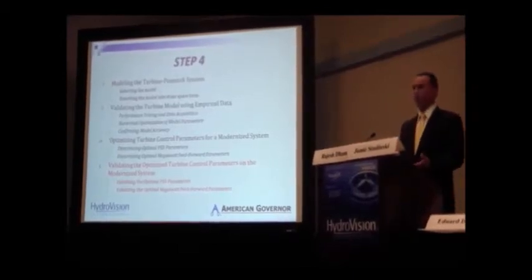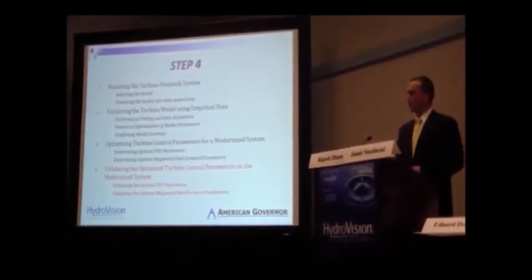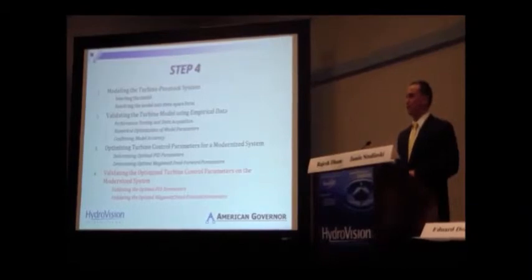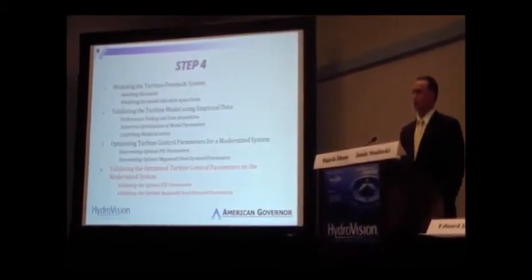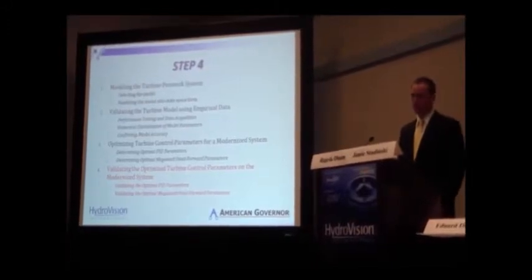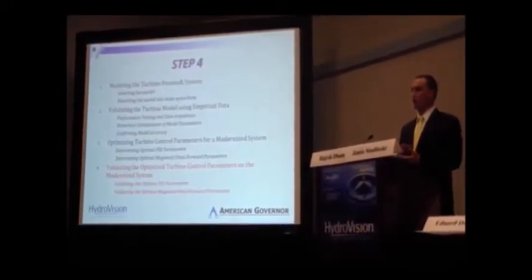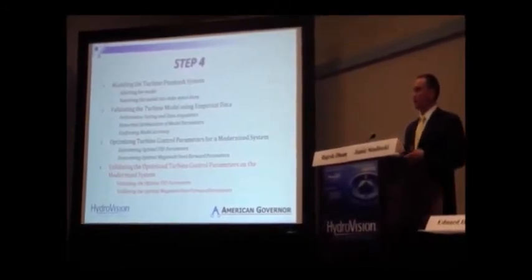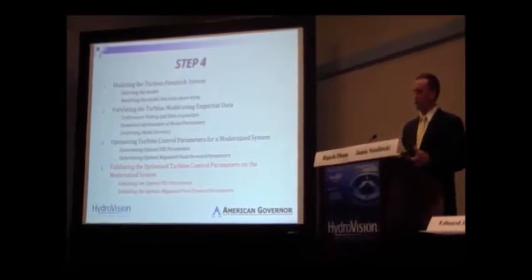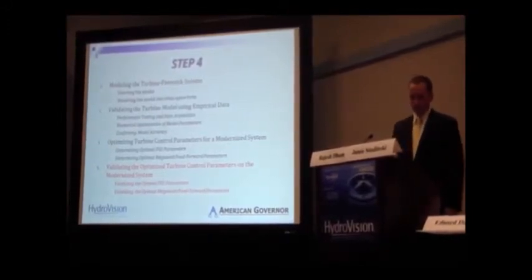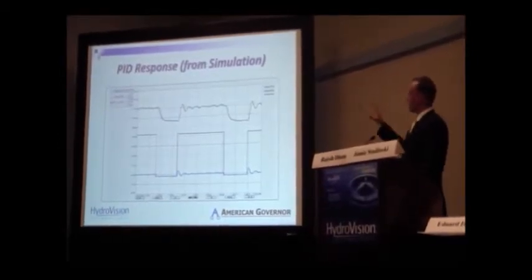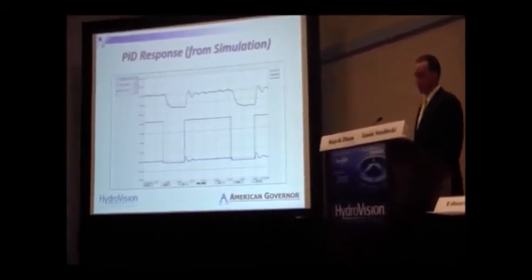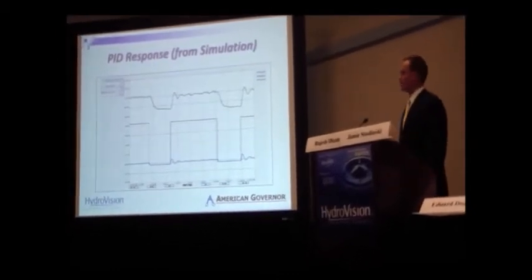The next step, which was really the rewarding part of the whole process, was being able to go back to that facility, and on that first commissioning of the new digital control systems we were putting in place, we were able to take a look at how our theoretical values, how our experimental values in the virtual world compared to that of the real world. And we can see here we have a few graphs just showing, this is on the unit itself with the gains as established through simulation.